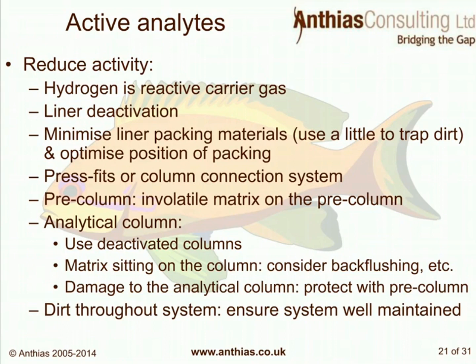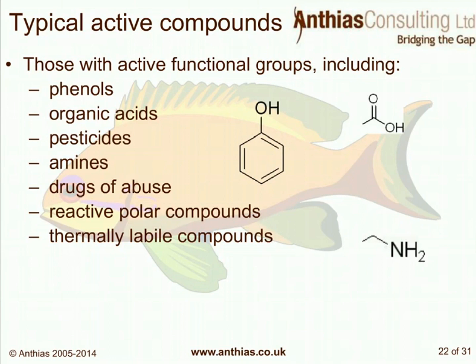Minimize liner packings — use a small amount at the bottom of the liner to trap dirt, and optimize the packing position to minimize activity with analytes. Any press-fit or column connection systems also need to be deactivated. The pre-column needs to be deactivated, but matrix sitting on it can cause activity — acting almost like extra stationary phase. The analytical column needs to be deactivated, and matrix sitting on it can also cause activity and damage the column, exposing silanol groups which are very active to these types of analytes. Consider backflushing to remove involatile matrix. Dirt throughout the system becomes very active and can lead to irreversible adsorption, catalytic breakdown, or peak tailing, which reduces signal to noise.